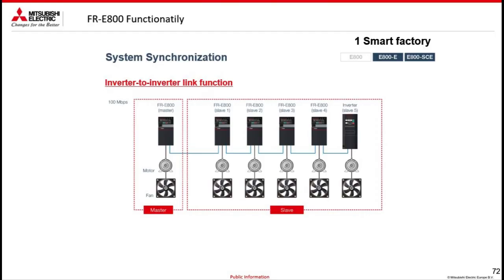We have a particular functionality, the inverter to inverter link function, that manages the integrated PLC and communicates with the different slaves. Doing so, for example, we can pilot the other inverters without the function of a master, because the master is the inverter itself. So I don't need a PLC. An example could be ventilation. I have the main ventilation, and if the temperature sensor goes beyond a certain value, so the ventilation done by the first one is not enough, I start slave 1, then if that is not enough, slave 2, slave 3, and so on.